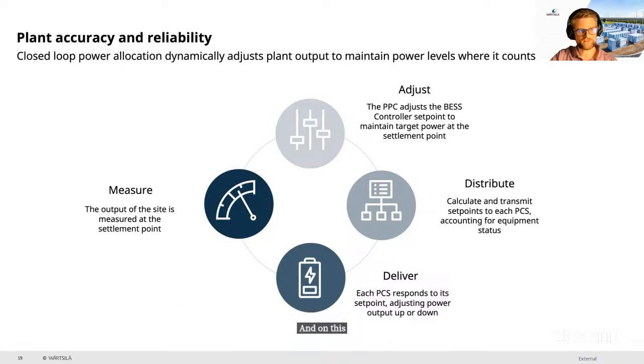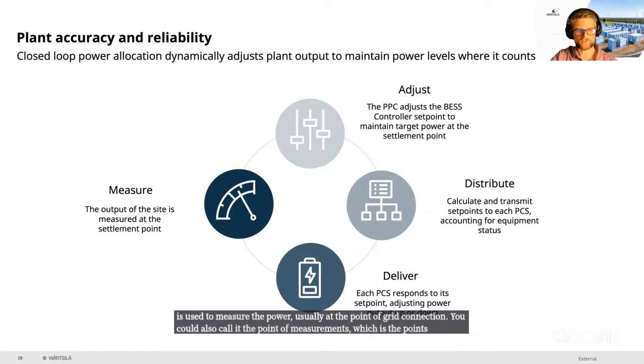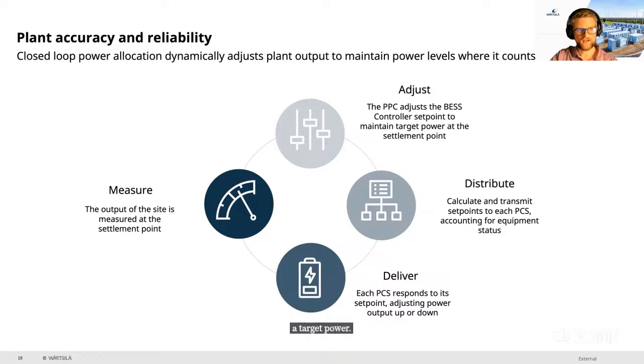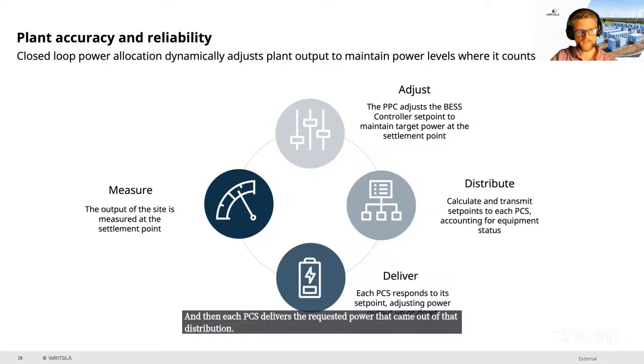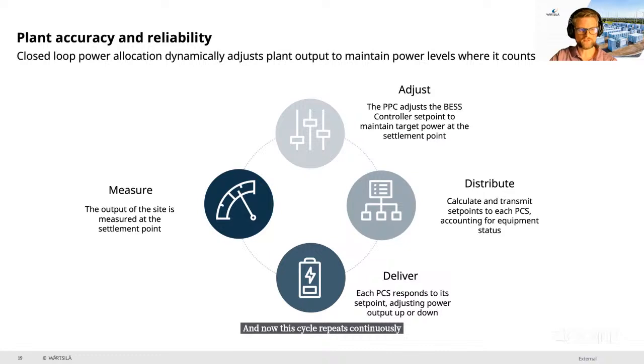On this slide, I have the general process for a closed loop controller. Starting with the measure part of the process, a power meter or a transducer is used to measure the power, usually at the point of grid connection. You could also call it the point of measurement, which is the point at which we're trying to achieve a target power. Then the controller adjusts the power set point for the BESS based on the error between the measurement and the desired target power. Then the PPC distributes that total power among all of the PCSs using power allocation algorithms, and each PCS delivers the requested power. This cycle repeats continuously, and each iteration happens 10 or more times a second. Next slide.